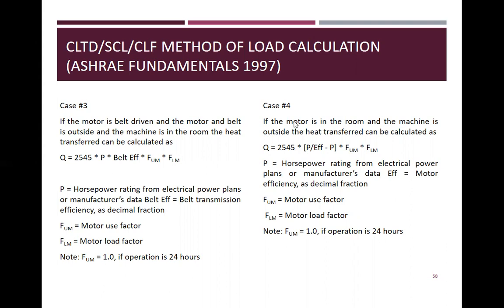So case number 4. If the motor is in the room and the machine is outside, the heat transfer can be calculated as 2545 times P over efficiency minus P, the difference, times FUM times FLM. Yung motor kasi nasa loob. So P is equal to the horsepower rating from electrical power or manufacturer's data, and Eff is the motor efficiency. FUM is the motor use factor, FLM is the motor load factor. Note, FUM is 1.0 if operation is 24 hours. Yan. Note yun lang. Nasa loob yung motor.